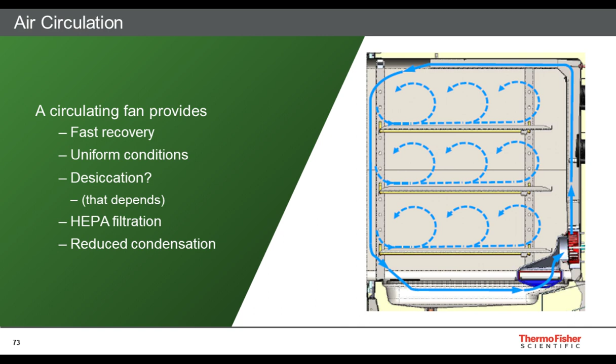And a circulating fan provides two additional benefits as well. You can provide HEPA filtration to capture airborne microorganisms that might be coming in from the laboratory, from the humans working in the laboratory. And a circulating fan reduces condensation in the incubator chamber. So condensation that would lead to microbial contamination, for example.